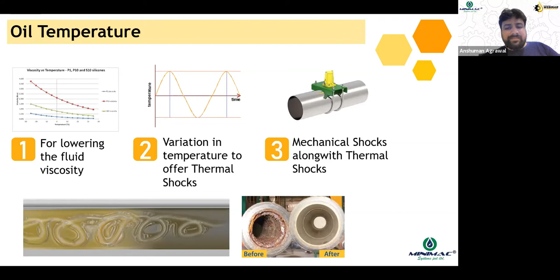Along with the thermal shocks, if you can perform some mechanical shocks using hammering or using mechanical vibrations, then the loosening effect would also help in dislodging the debris into the flushing fluid. So you can see the picture below. There is a pipeline which is due for flushing, and it has a lot of rust and debris in the internals. After flushing with proper methodologies, the pipeline you can see is as clean as a new pipeline.